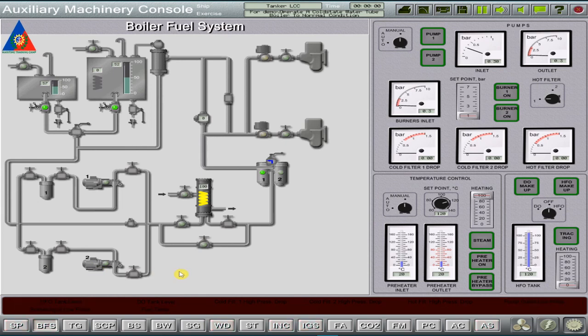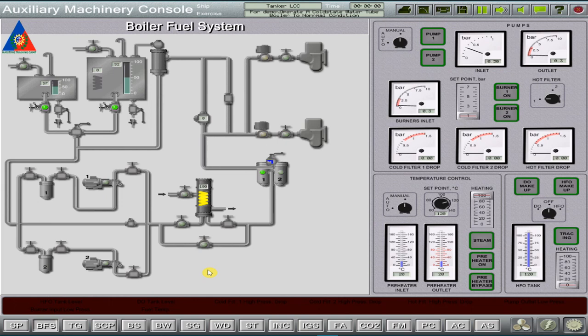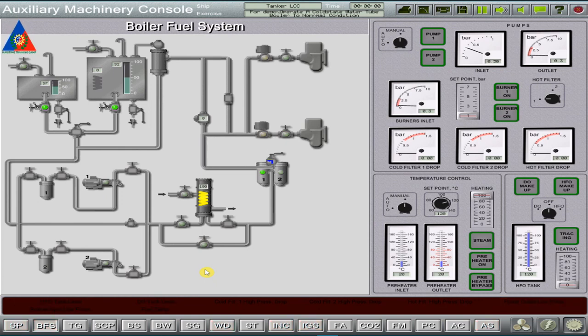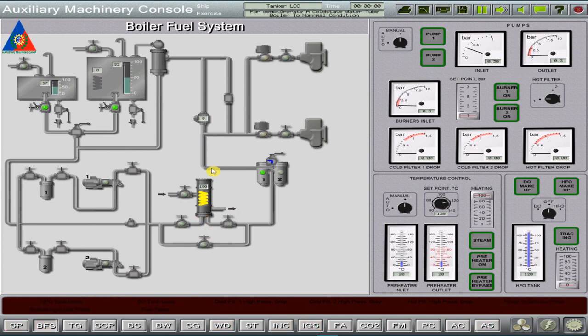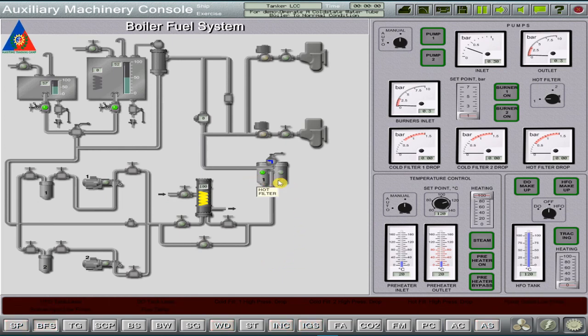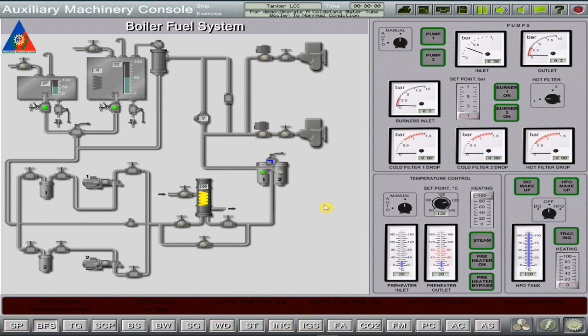One in operation, the other on standby. The fuel is fed to the burners which is under certain pressure, under temperature which ensures the fuel viscosity of 10 to 15 centistokes required for adequate fuel atomizing by the burners. And through the filter, which guarantees separation of solid particles of more than 50 microns to prevent the burner clogging.